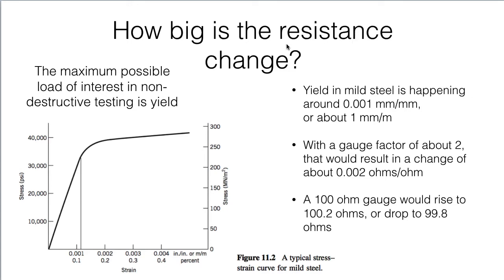So how big is that resistance change going to be? Well, the maximum possible load of interest in non-destructive testing is going to be when we would be getting up towards the yield strength of the material. We don't want to bend things permanently. So we're looking at only about one part in a thousand change in the size of something. So very small changes in size. That'll result in about twice as large a change in resistance. So if our gauge factor is about 2, we'll wind up with a change of about 0.002 ohms per ohm. Or if we had a 100 ohm strain gauge, it would rise up to about 100.2 ohms or drop down to about 99.8 ohms. So a very small change in resistance. And how are we going to be able to measure that?